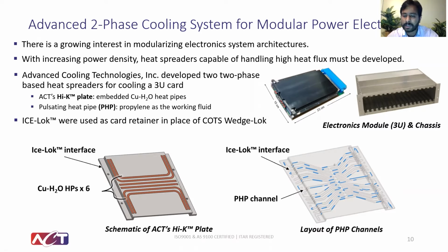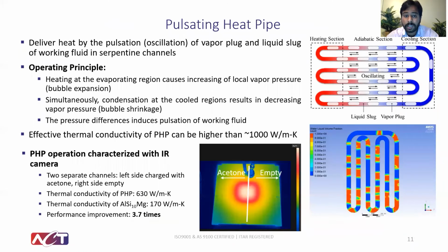One is the high K plate, which has embedded copper water heat pipes in an aluminum plate. The other is a pulsating heat pipe with propylene as the working fluid. We did performance testing of the cooling system with these two heat spreaders and compared it to the baseline case, being an aluminum plate as the heat spreader. In the performance testing, we used an ice lock as the card retainer in place of a COTS Wedge-Lok. In this slide, I'll be introducing the pulsating heat pipe that was developed in this program.